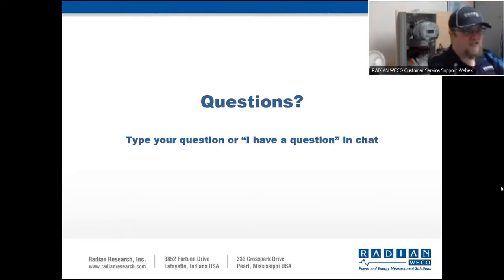CT is. For example, these CTs behind me are 1 under 5 CTs that we've been using around here for a while. They've never been exposed to any kind of lightning strikes or anything, like their office CTs that we use. And I just ran a DMAG on it today. The ratio didn't change. Nothing changed with that ratio because these have never been out in the field. They've never been in true three-phase service. So it depends on the situation. It depends on the site. It depends on what that CT has been through to affect its ratio.